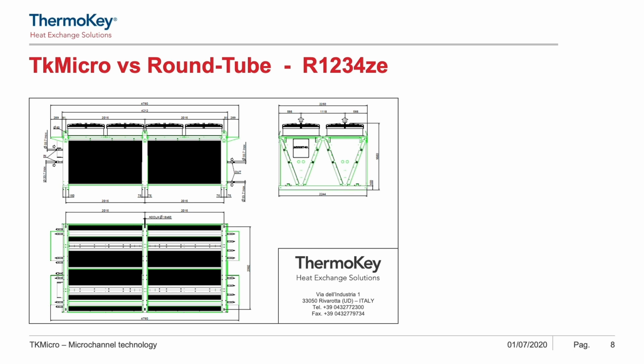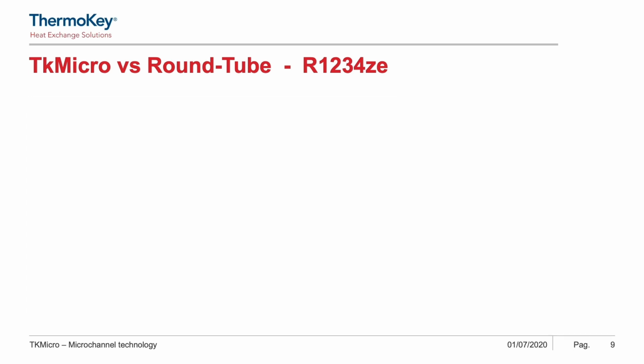Another good example of the advantages of the microchannels, in particular in the case of electrically driven chillers, is a comparison based on R1234ZE, more and more used HFO refrigerant. In this case, we have analyzed a remote condenser of 470 kilowatts. And again, as in the previous case, we've compared weight and all other aspects.